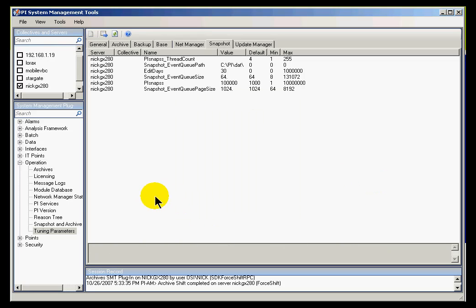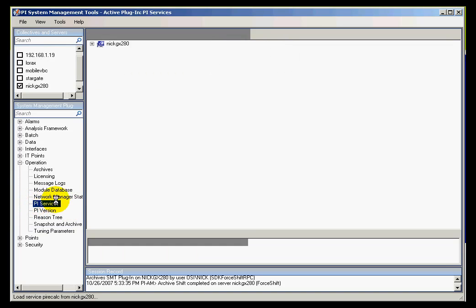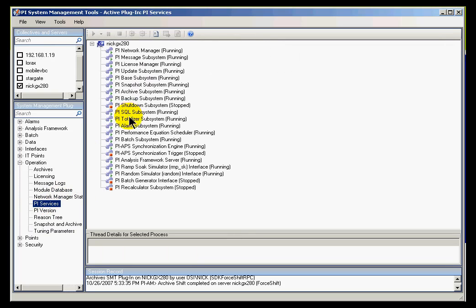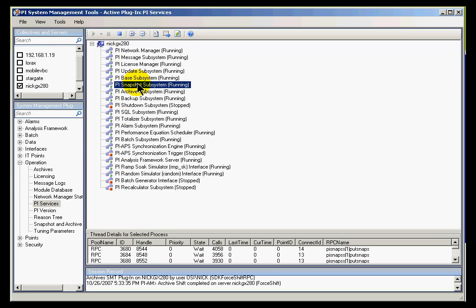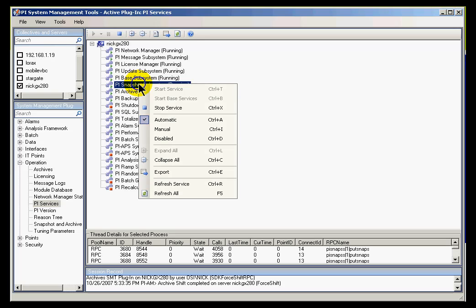Now, as I said, that's not going to actually take effect until you go into the Services applet. And within Services, we're going to stop and restart the PI Snapshot subsystem. So here's our PI Snapshot subsystem. I can stop this and then restart it.